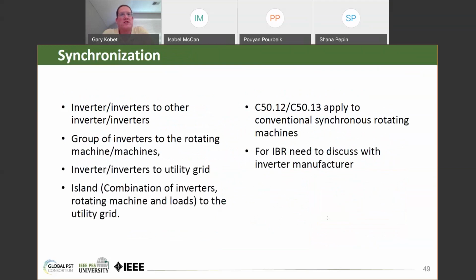Synchronization is also a topic that is touched on in the working group of the task force paper. And the bottom line here is that the inverter manufacturer has to be consulted. There are a couple of industry standards, C50.12 and C50.13, that apply to conventional, synchronous machines, but for IBR, the idea of synchronizing inverters to inverters or groups of inverters to rotating machines, those synchronization requirements have to be discussed with the inverter manufacturer.